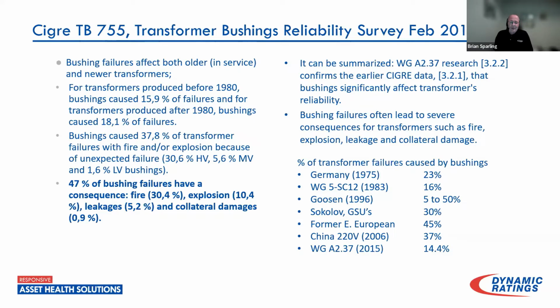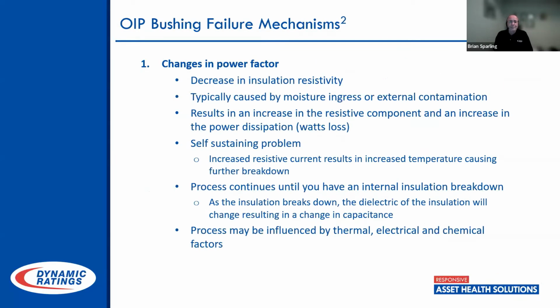So when we look at the failures of transformers, a higher propensity of failure of the transformer is due to one of the bushings on the transformer. And when you look at the data from that study, looking at the transformer failures caused by bushings in different parts of the world and different times, there's quite a higher number of transformer failures where the root cause was failure of the bushing.